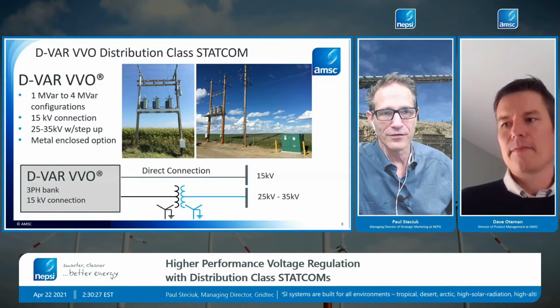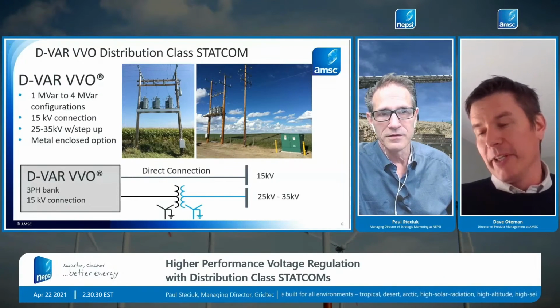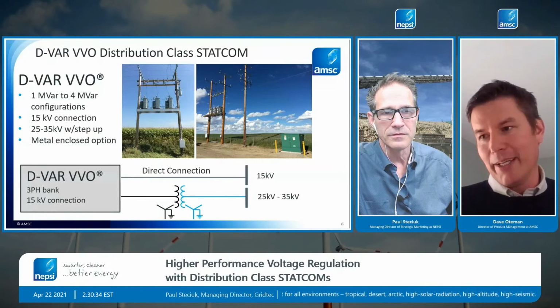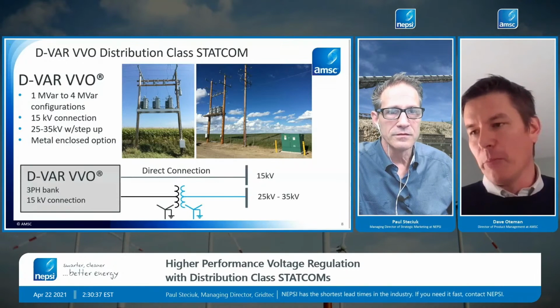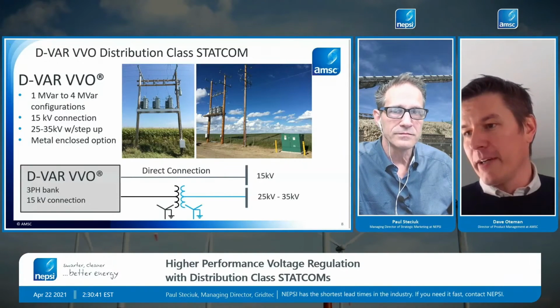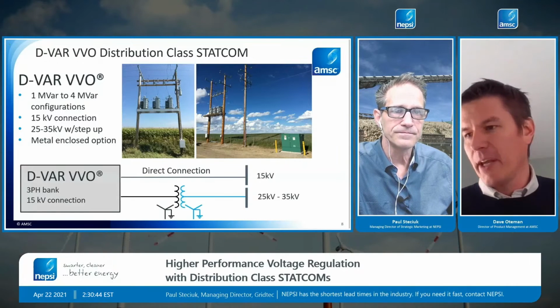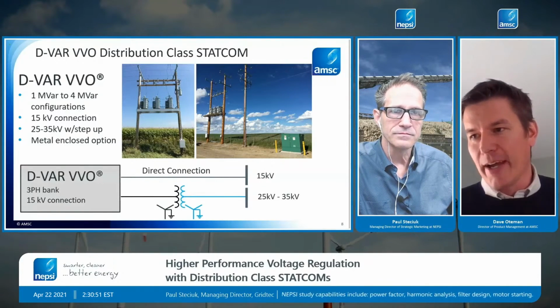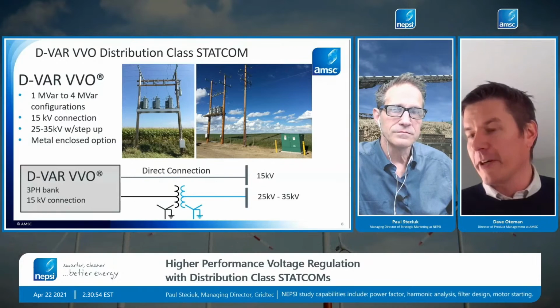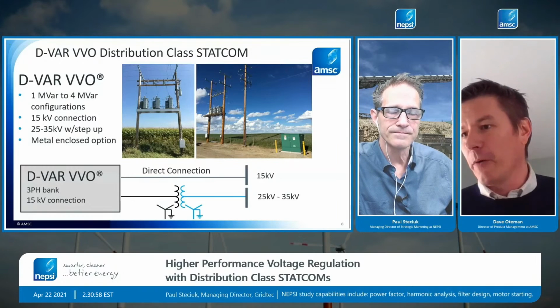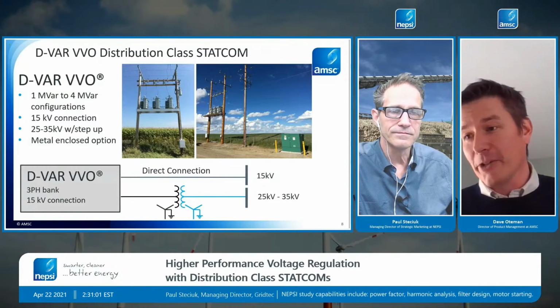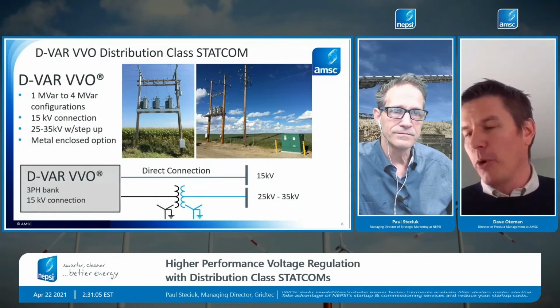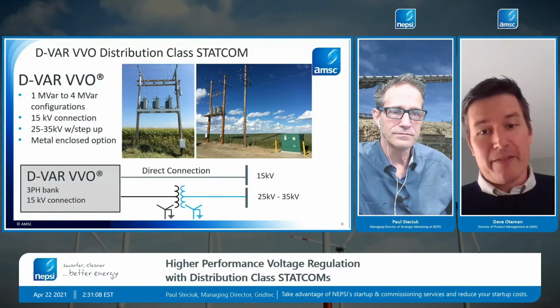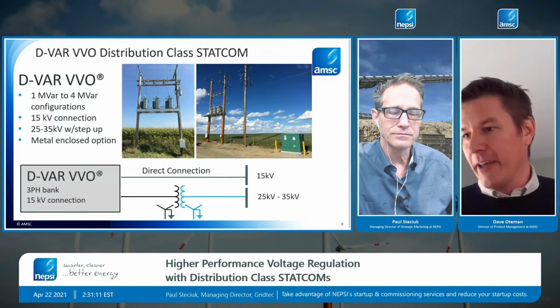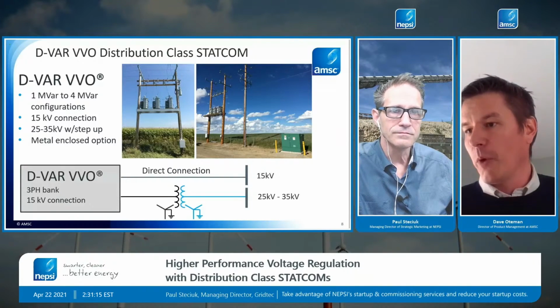Is that a fair possibility? It is, and we'll show later how to think about that. The short answer is, for upstream regulators closer to the substation, within the first protection zone, those typically need to remain installed. But where the STATCOM really shines is on the downline portions of a feeder, 7 or 8 miles or longer down line, some feeders are 20 miles. Anywhere along those downline portions, it's possible to replace the line regulator altogether and get all the benefits we covered.